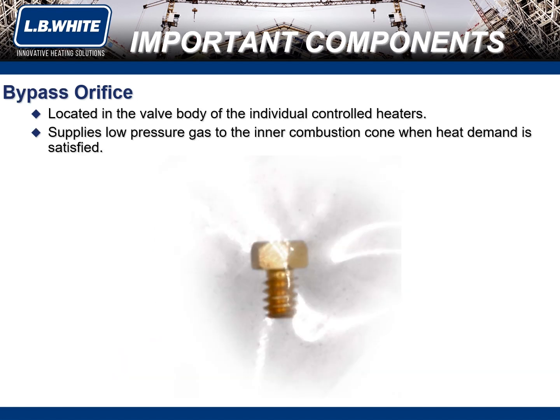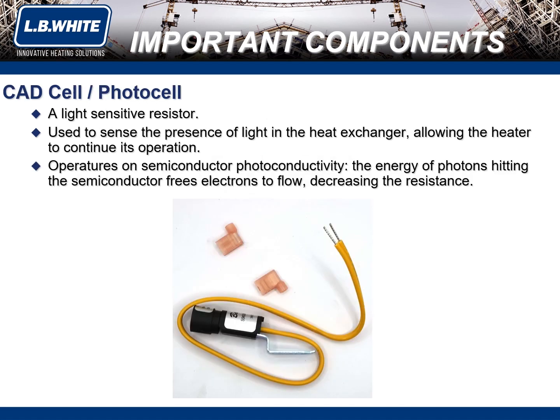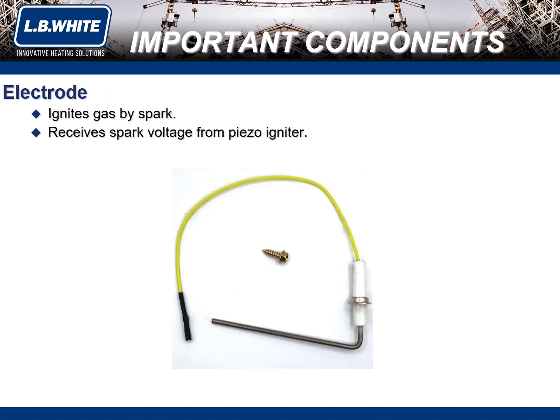A bypass orifice is located in the valve body of the individual controlled heaters. It supplies low-pressure gas to the inner combustion cone when the heat demand is satisfied. A CAD cell is a light-sensitive resistor. It's used to sense the presence of light in the heat exchanger, allowing the heater to continue its operation. An electrode ignites gas by spark. It receives a spark voltage from a piezo igniter.